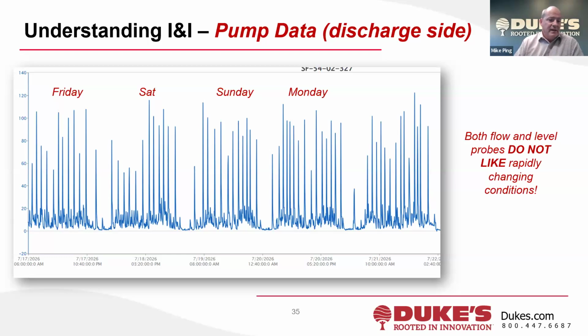Then during the day you see radical changes. The pumps turn on, and there's basically a slug of water coming over the hill on the discharge side. This hardware is built to wake up every 5 minutes, record a snapshot, and then go back to sleep for 4.5 minutes or whatever. It's just not built for that.